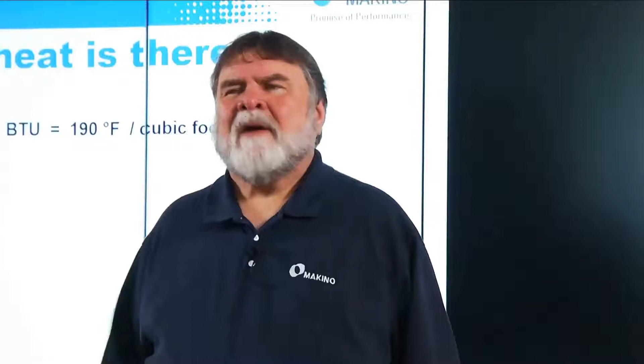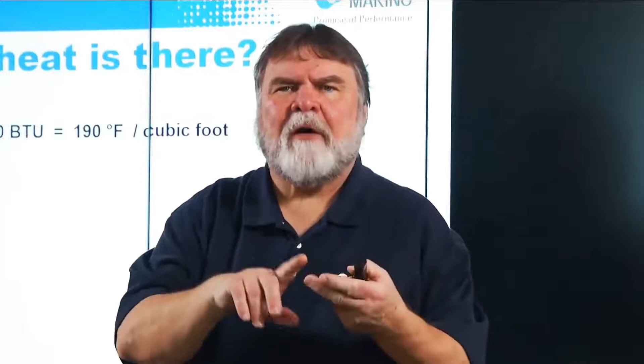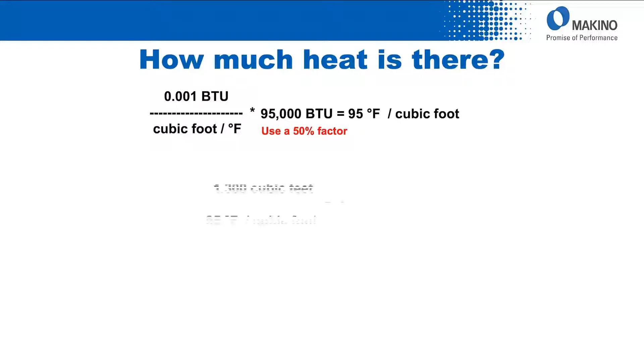Well, that's not really fair, because if you think about the machine, the spindle motor's not running all the time, the servo motors aren't running all the time, the coolant pumps may not be running all the time, the hydraulics, so that's kind of an overstatement. Let's get more realistic. Like I said, that assumes 100% of the time. Let's use a 50% factor. Let's take that 190 down to 95. All right, well then it comes up to 95, 96 degrees per cubic foot.